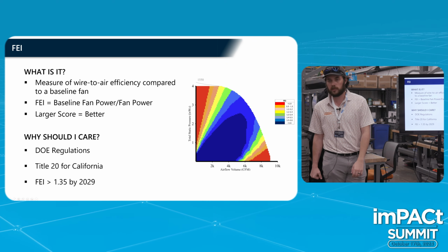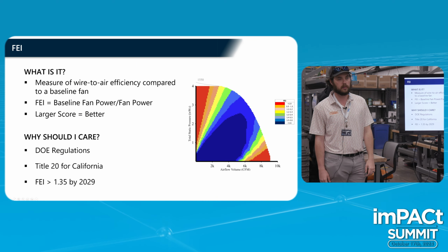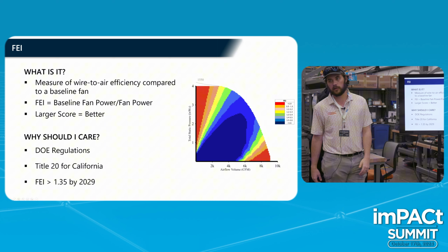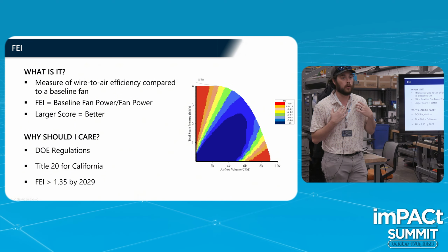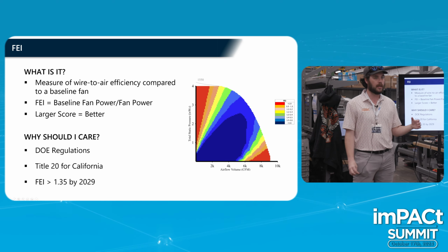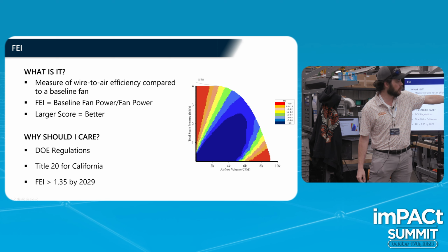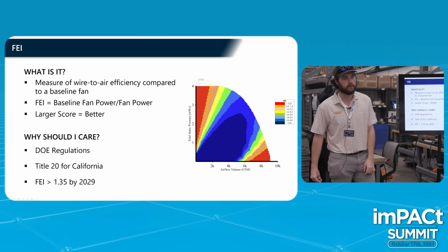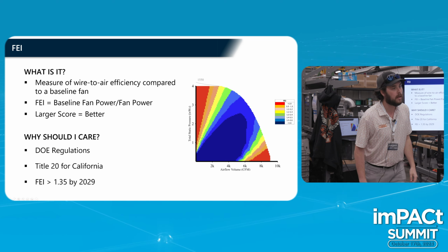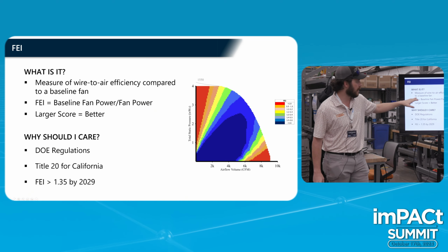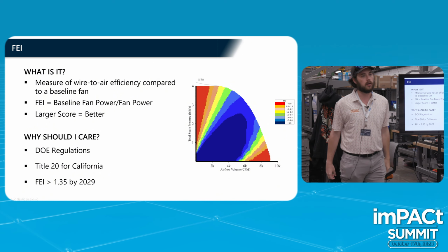terrifying for a lot of companies, but luckily we have this really awesome technology that already has really high FEI scores in most applications. So they even sell it, manufacture it? Yeah, so we will not be legally allowed to sell a system. If you tell me your operating point is up here, I could not sell you the system. So. It's still at one operating point? Yes, so the FEI is at the specific operating point that you're designing it for.